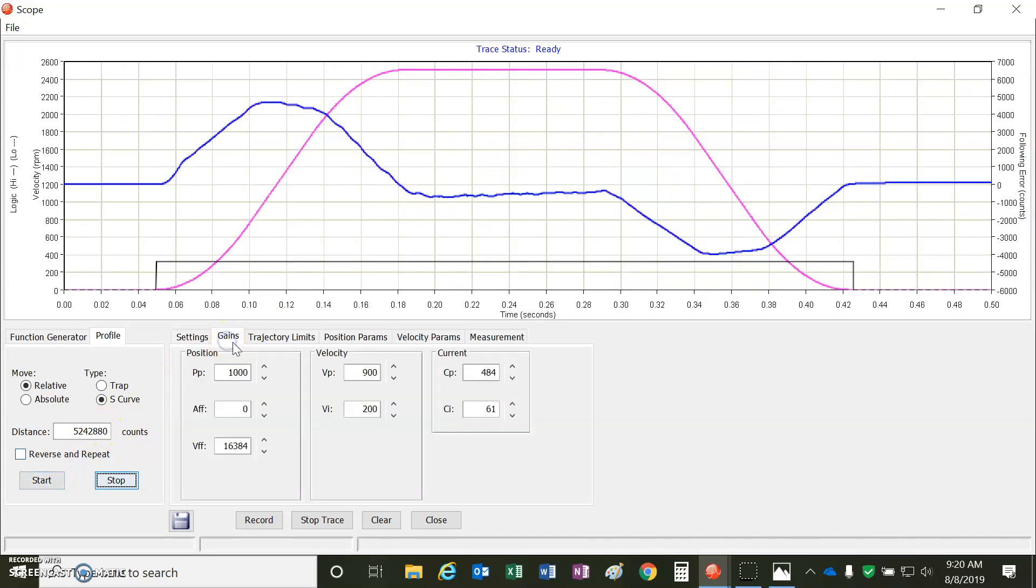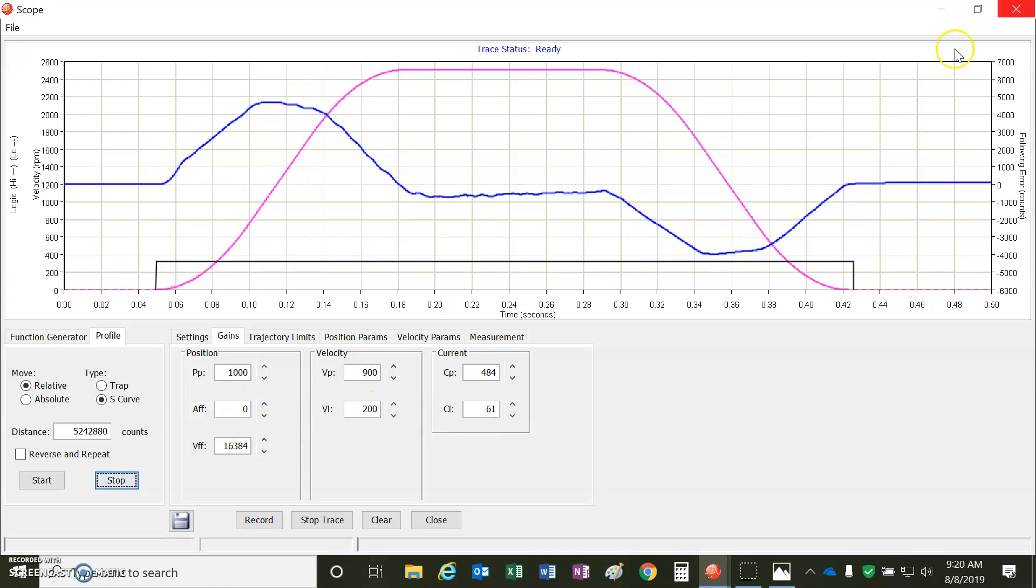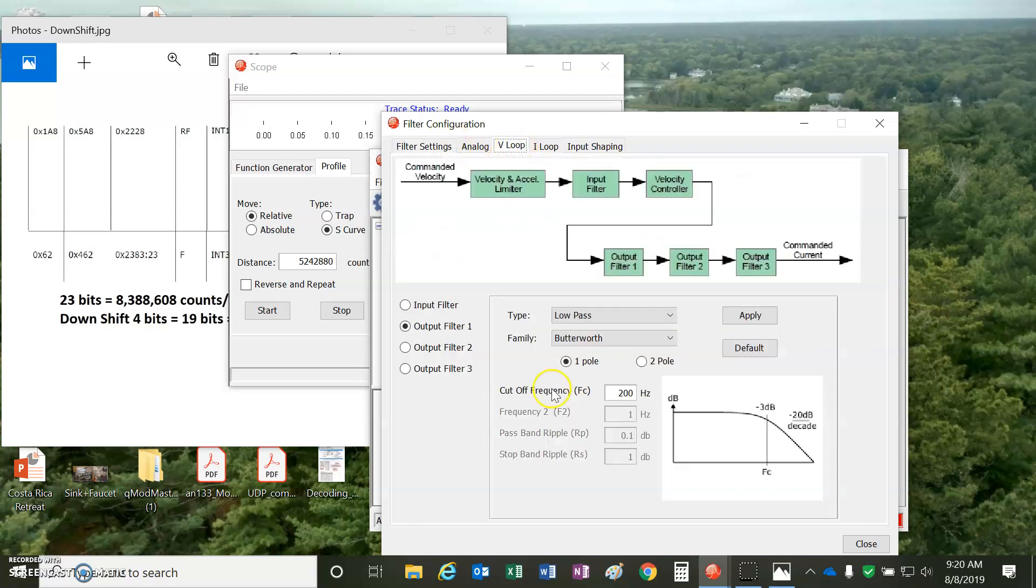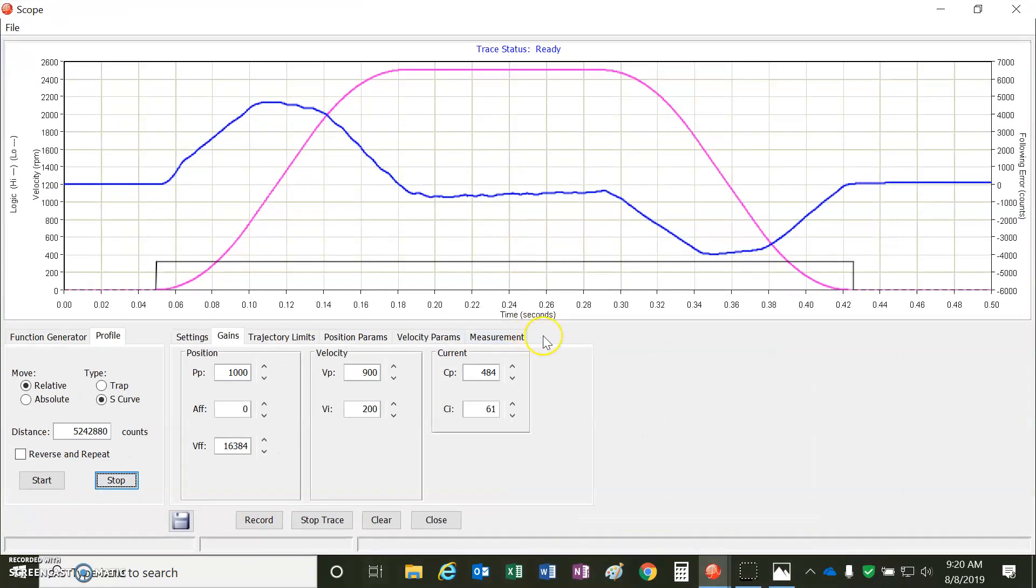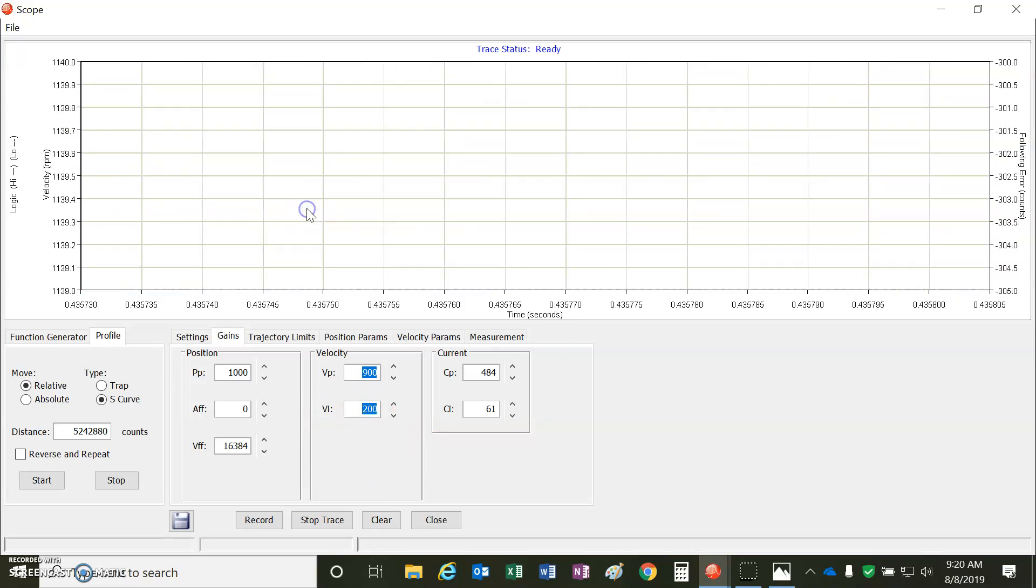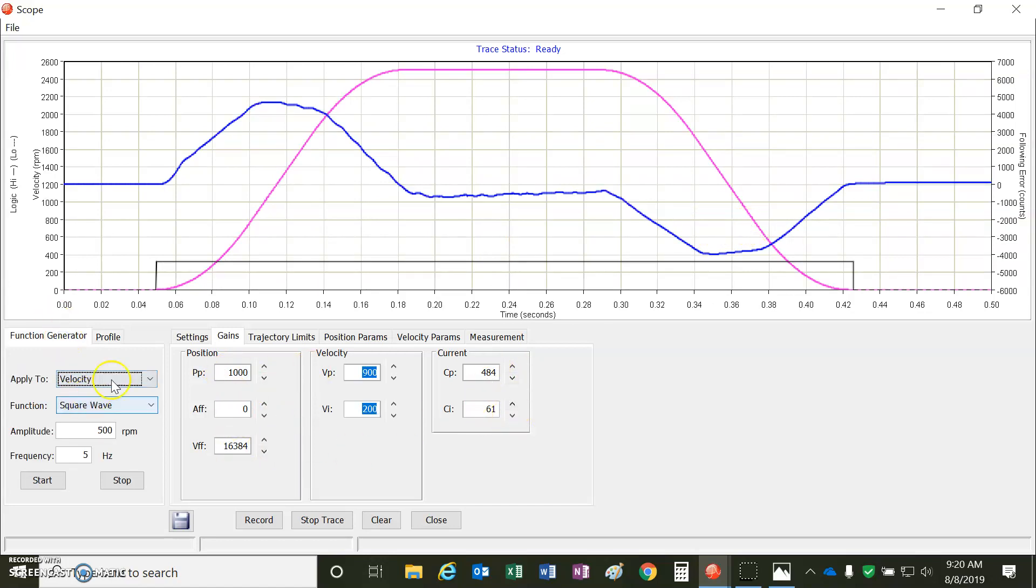Taking a quick peek at the gains here, I just left the position at default. If we had a large mass, we'd bring the PP down. I tuned up VP and VI. I also moved the filter from a two pole to a one pole. So on the V loop, I picked one pole and hit apply. That gave me the ability to increase the VP a little bit. I tuned the velocity loop integral based on the settling here. So that's the default for this. So let's take a look at the current loop tuning and see if we get a little bit more current loop bandwidth out of it.